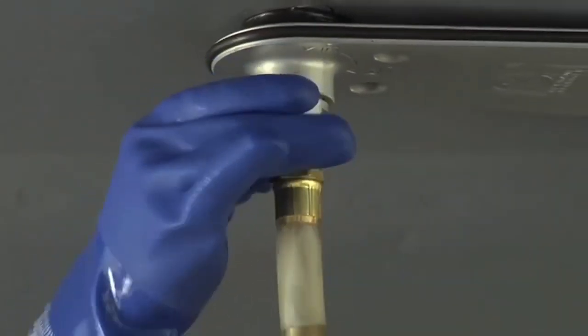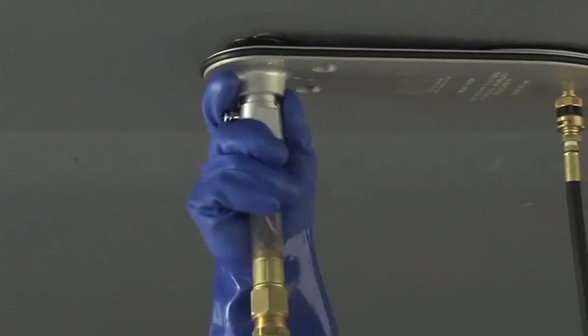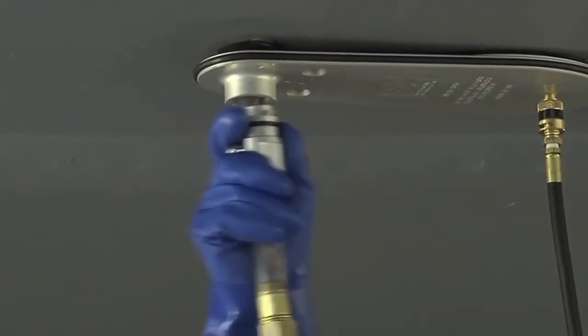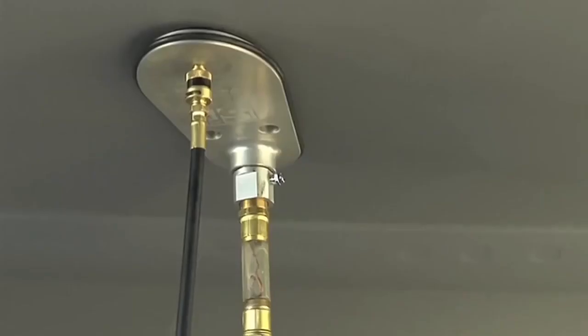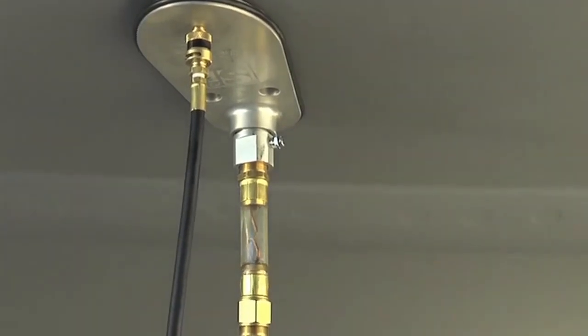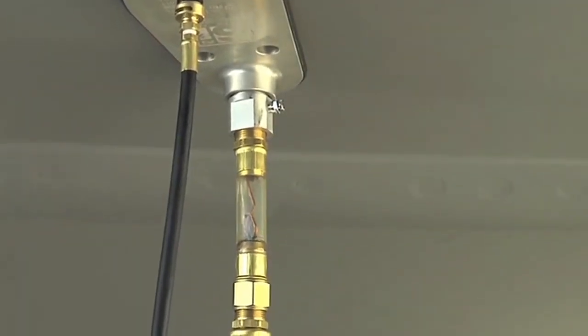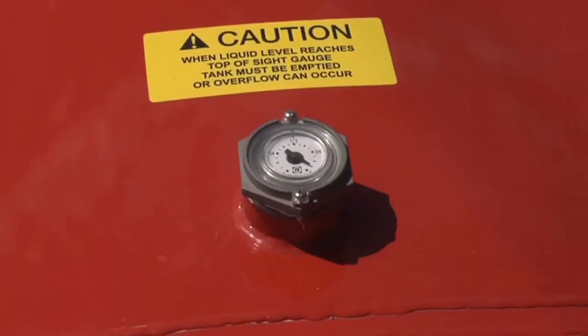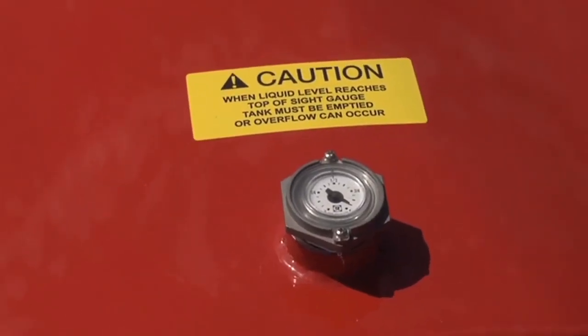Another safety note: if you should need to pause draining operations, ensure the drain hose is removed from the drain tool assembly as previously described. Fuel can gravity drain down the hose, even with vacuum turned off and the air source disconnected. This could result in the tank overflowing.